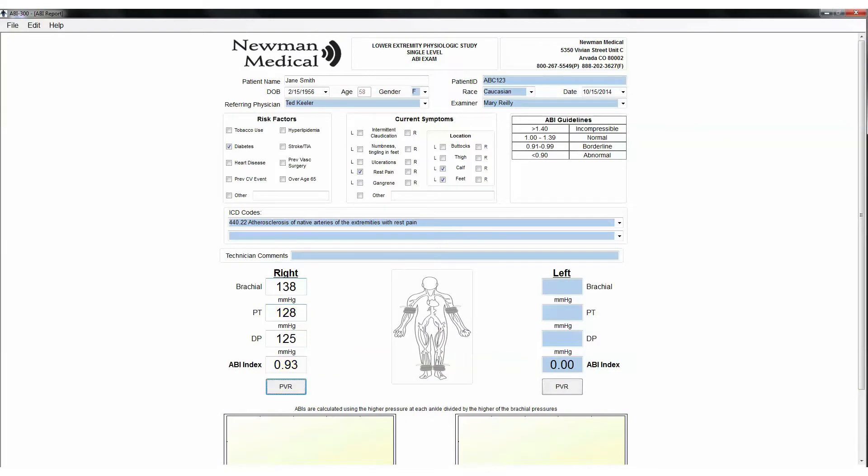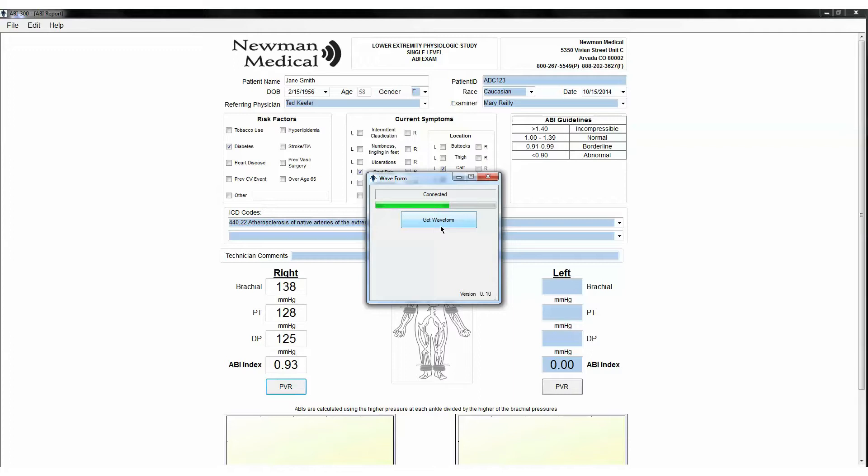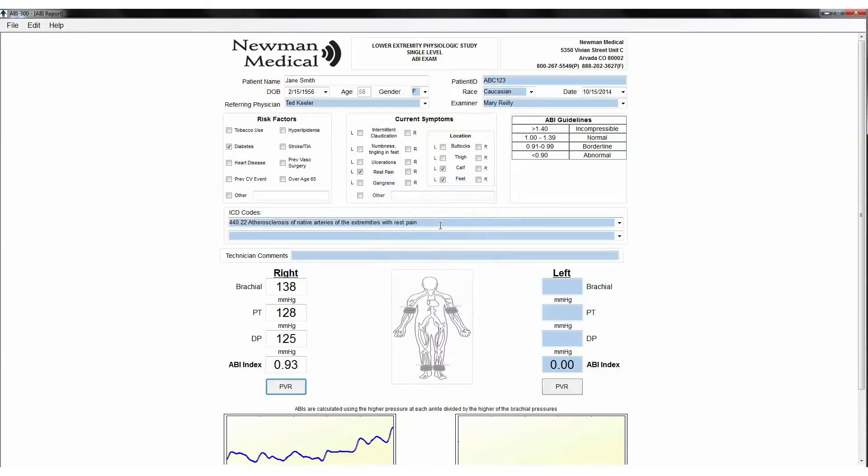If you are satisfied, release the pressure from the cuff. To obtain a PVR waveform at the ankle cuff, press the right PVR button on the computer screen located under the right ABI index. A pop-up will appear with a visual gauge of appropriate pressure. Inflate the cuff to approximately 80 mm and deflate to 65 mm. This slight overinflation helps to release wrinkles in the cuff and take a more stable PVR waveform.